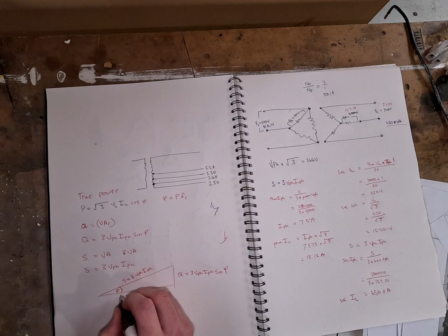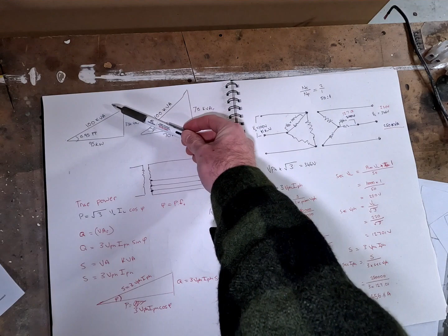As a last thing for this video, I drew a diagram showing how power factor affects how well a transformer works. Look at this first triangle: a 100 kVA transformer with a power factor of 0.95. That means the true power is 95 kilowatts with a kVAR of 31. That's producing pretty well, close to its apparent power.